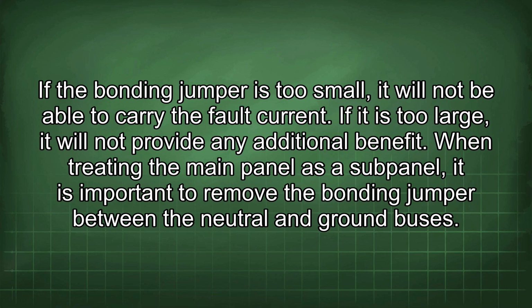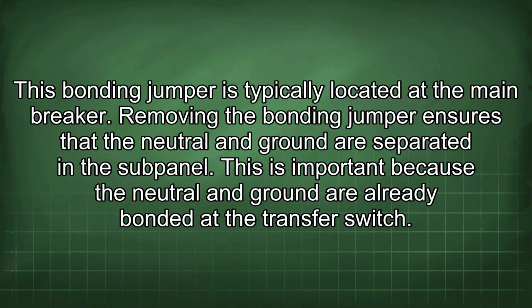When treating the main panel as a subpanel, it is important to remove the bonding jumper between the neutral and ground buses. This bonding jumper is typically located at the main breaker. Removing the bonding jumper ensures that the neutral and ground are separated in the subpanel. This is important because the neutral and ground are already bonded at the transfer switch.